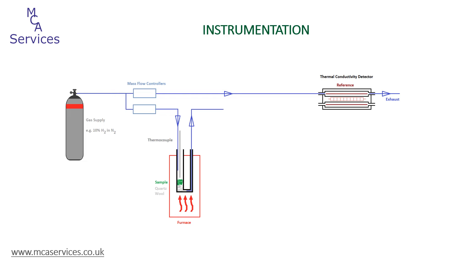The gas stream is split into two and each side passes through its own mass flow controller. These enable us to select the gas flow rates passing further onto the instrument, and in the vast majority of cases we will select these to be matched. The stream passing through the top mass flow controller passes directly to the TCD reference channel and across the TCD filament and then out through exhaust. The gas passing through the bottom mass flow controller forms the analysis stream and this passes through the sample tube.